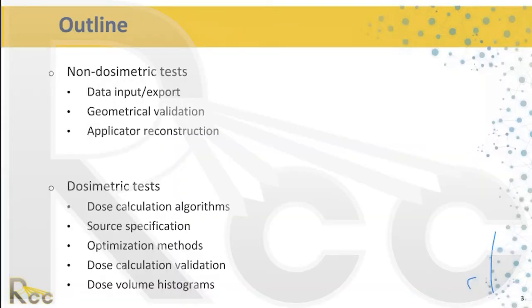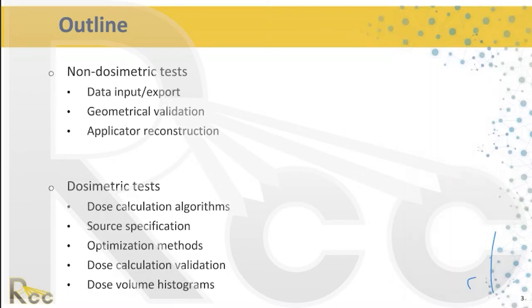We can broadly classify the commissioning process across two categories: non-dosimetric tests and dosimetric tests. Anything not directly affecting the actual dosimetry or modeling is a non-dosimetric test — that includes input and export of data, and geometrical validation. Once done, the important thing is to assess the accuracy of the dose calculation, source specification, optimization methods, and other features of the planning system. Both steps are critically important.